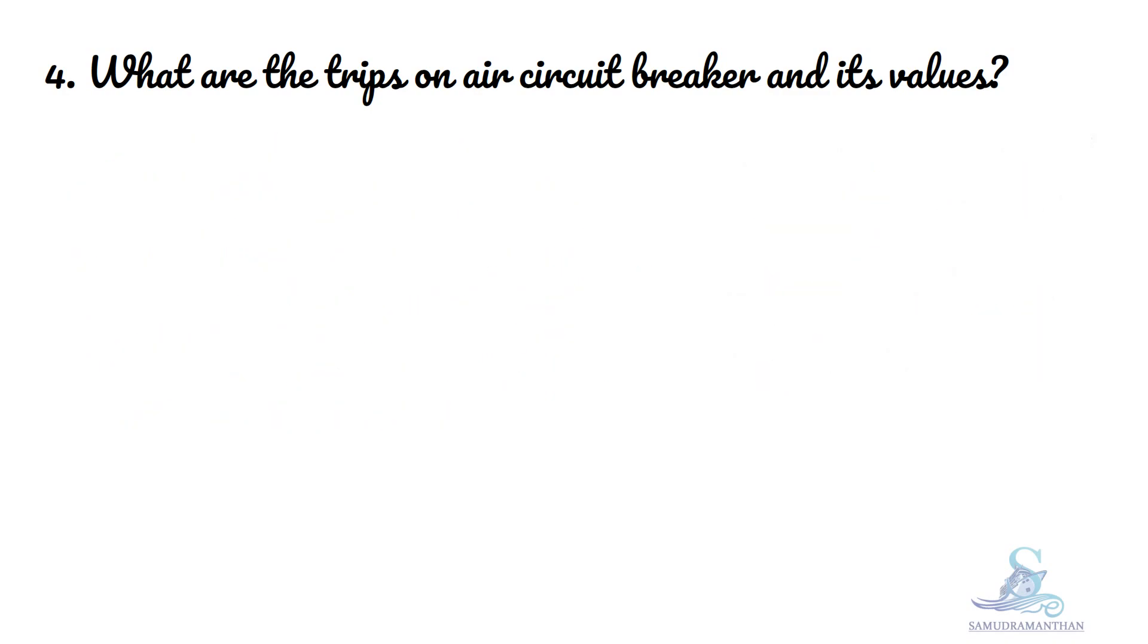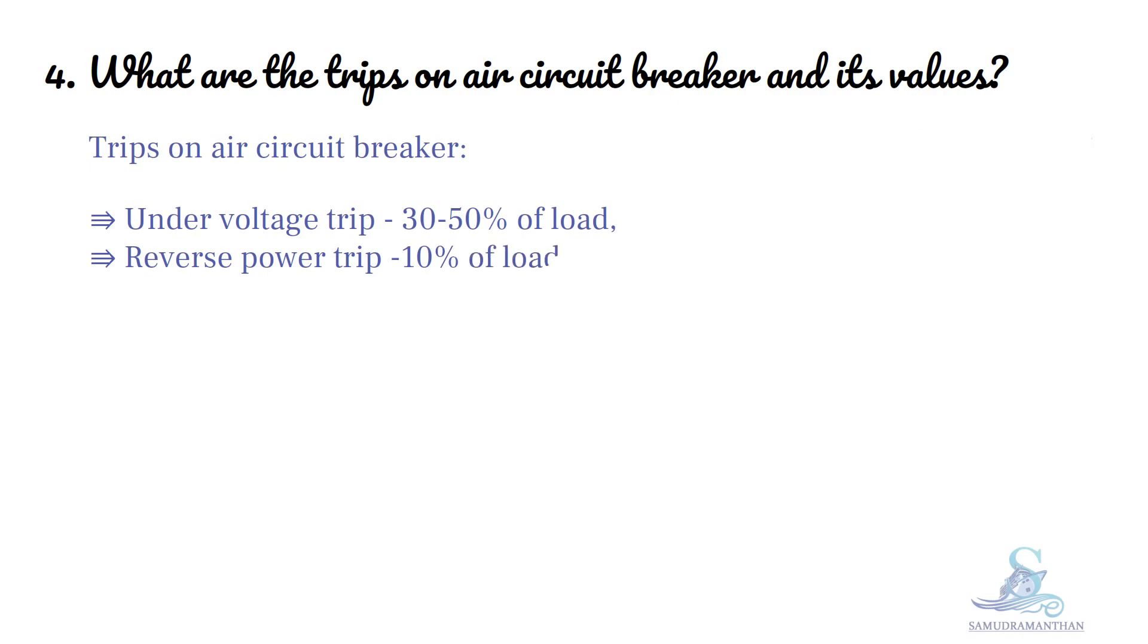Now let us discuss the different types of trips on an air circuit breaker. Under voltage trip: 30-50% of load. Reverse power trip: 10% of load. Short circuit trip. Over current trip: 150% of full load current.